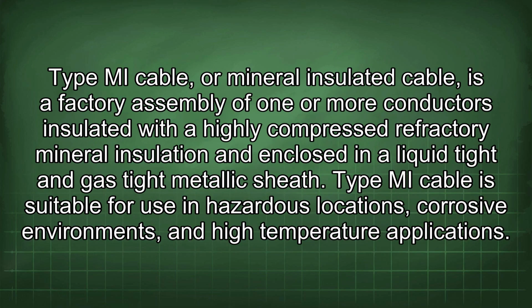Type MI cable, or mineral insulated cable, is a factory assembly of one or more conductors insulated with a highly compressed refractory mineral insulation and enclosed in a liquid-tight and gas-tight metallic sheath. Type MI cable is suitable for use in hazardous locations, corrosive environments, and high-temperature applications.